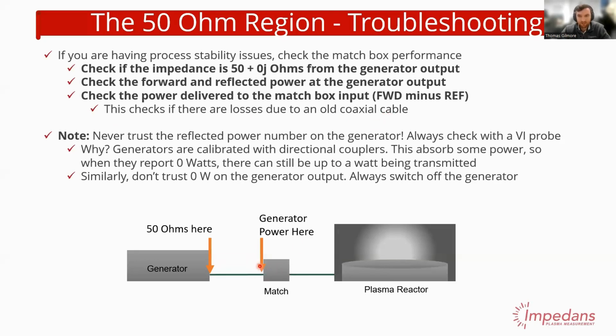I think it's standard practice in most fabs that if you're calibrating a generator and there's a long cable, you calibrate the generator to the point at the input of the match. But if you don't do that, or you're in a research lab and only look at the generator output numbers, don't do that.